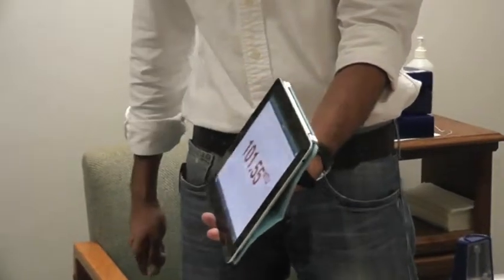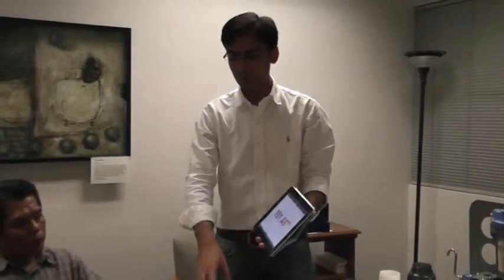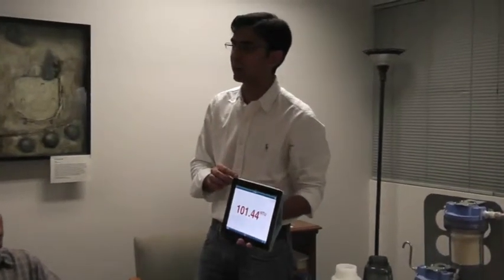So this is just part of your calibration. You're calibrating it yet? I'm not calibrating, I'm just showing that, because we know the value of it, so I want to show the accuracy of the system right now. Because the calibration allows you to get a range, right? This is like a spectrophotometer, right? Yeah, it is. I remember with a spectrophotometer, we got the small range because the thing that we were measuring was very, very light. That's for accuracy, but those we do in our high-tech systems, we get to like 0.1 NTU accuracy. In this one, the variation or the error is more than that. So maybe a 1 NTU error is not a big deal in this unit.